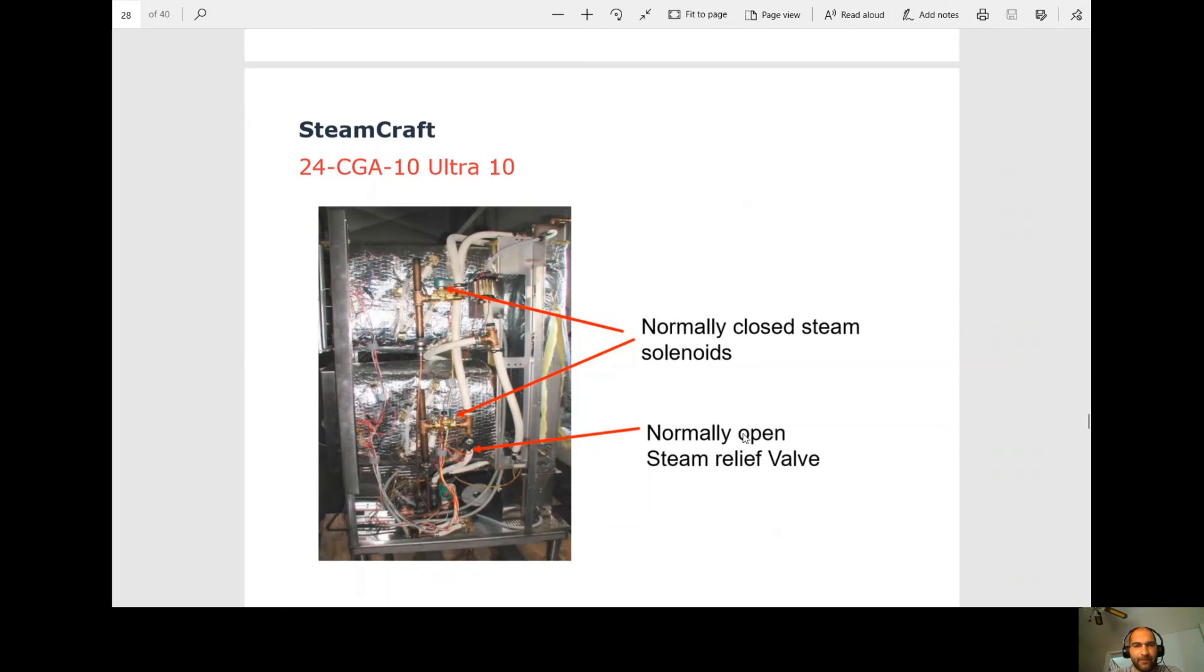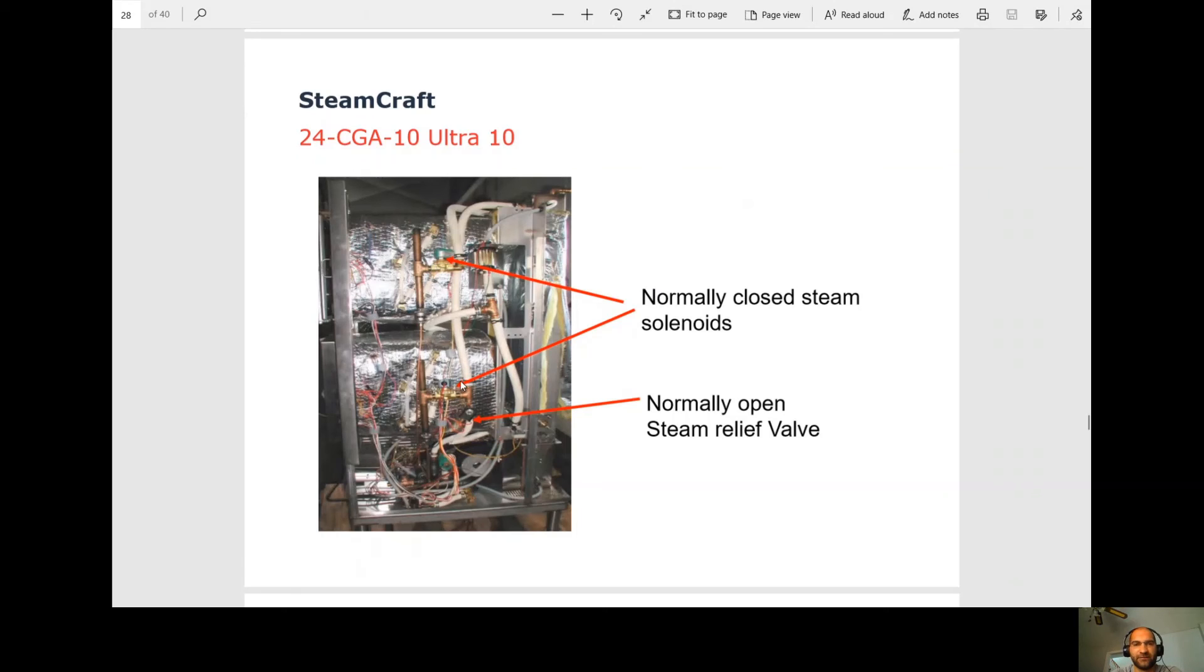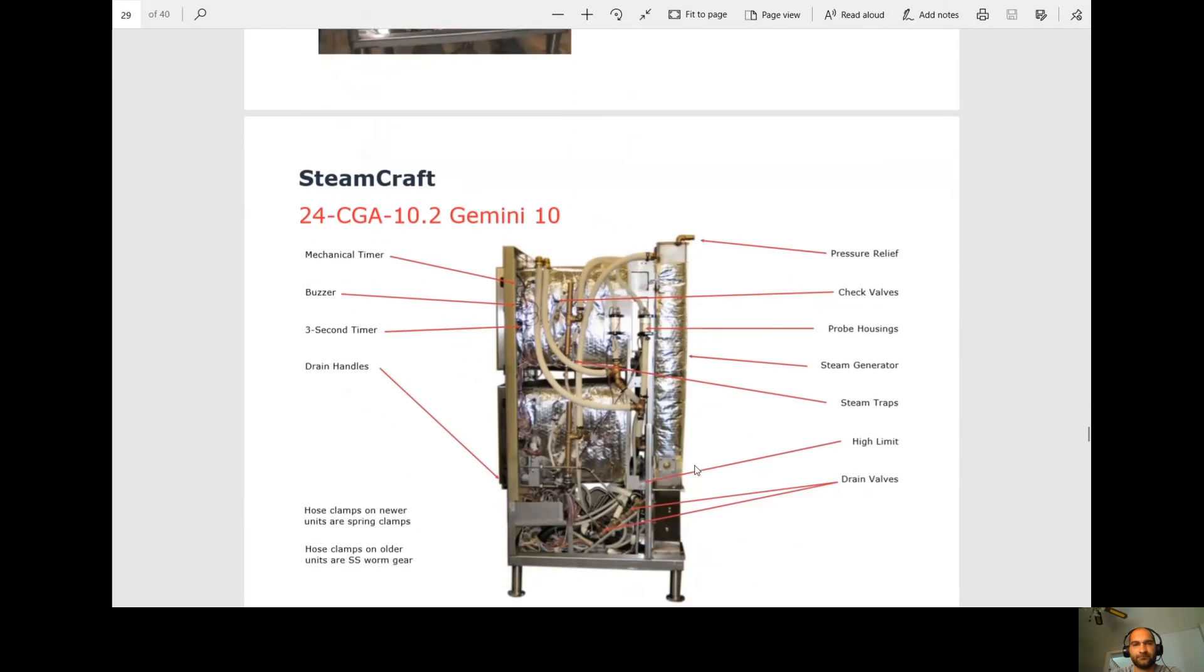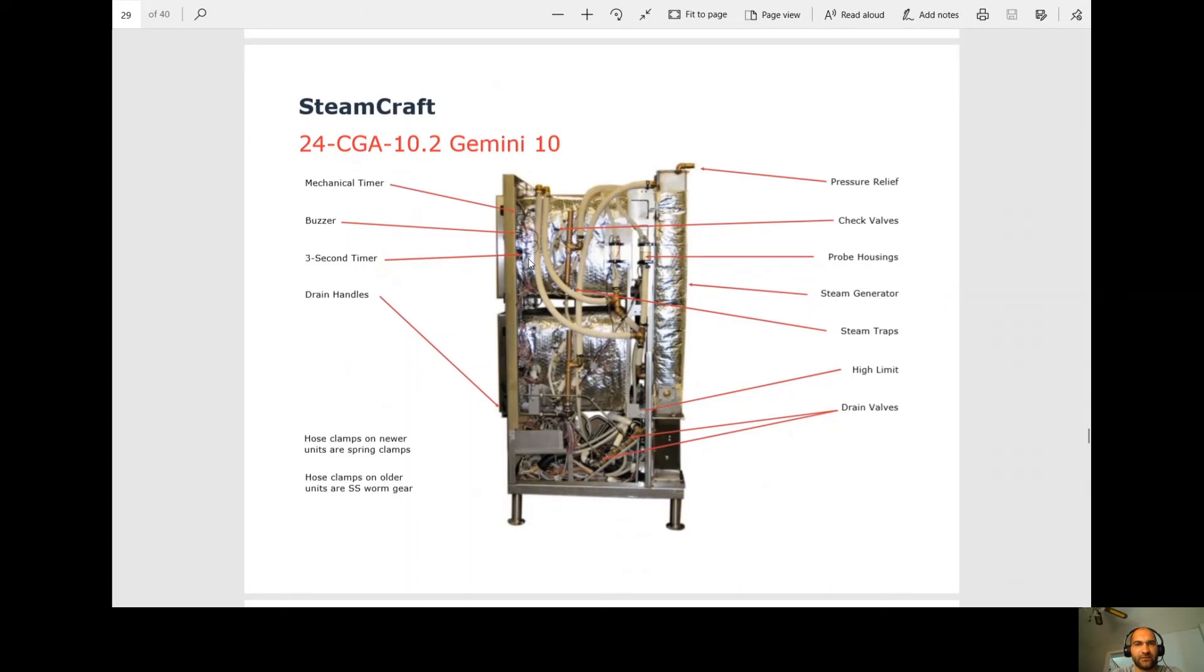So this is the steam craft unit. Just quickly, these are the steam solenoids. That's allowing steam into there. And then these are the relief valves. This is going down at the drain. So that's how we're controlling how much steam can go into the cabinet. We have the mechanical timer at the top, the buzzer, our three second timer. The drain handles. Your drain valves in the back here. Your high limit in the back as well. We have our steam traps. Here's the steam generator or the boiler. Probe housings, the check valves, and then our pressure relief here, which we always need those on a boiler because if we always over pressurize, that thing basically becomes like a bomb. So we want to be able to release the pressure at a certain pressure so we don't build up too high.